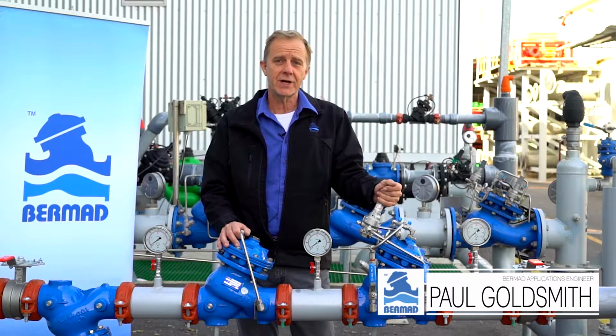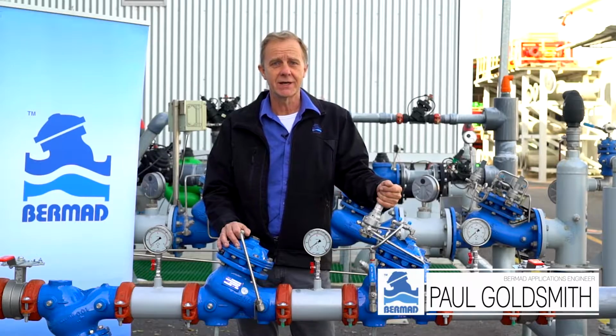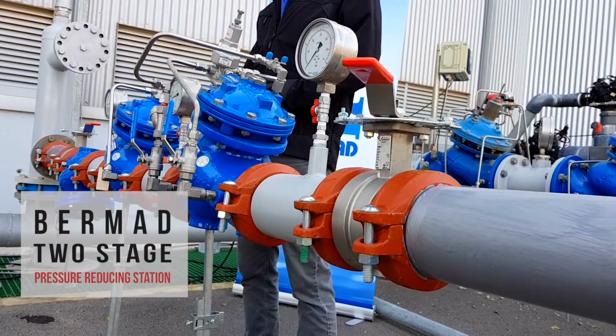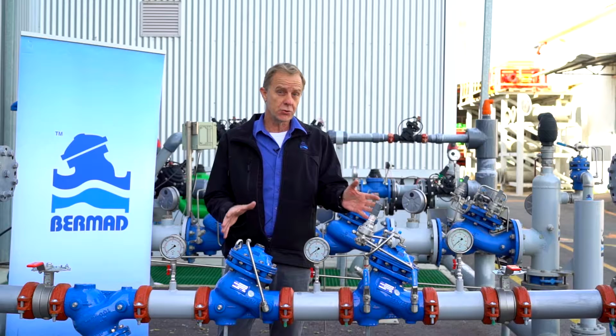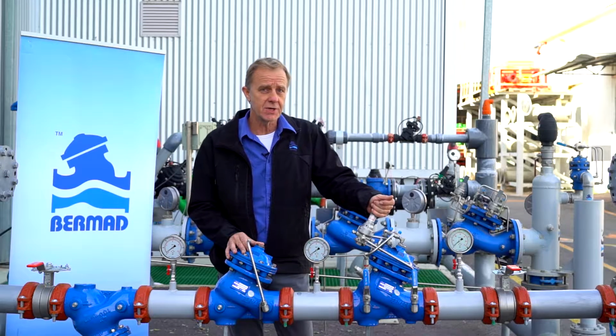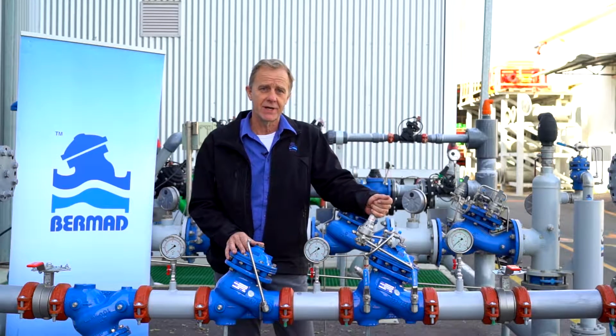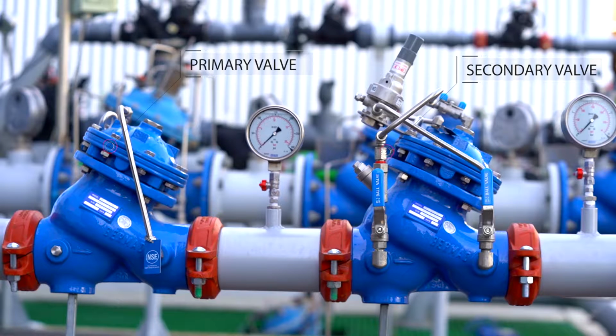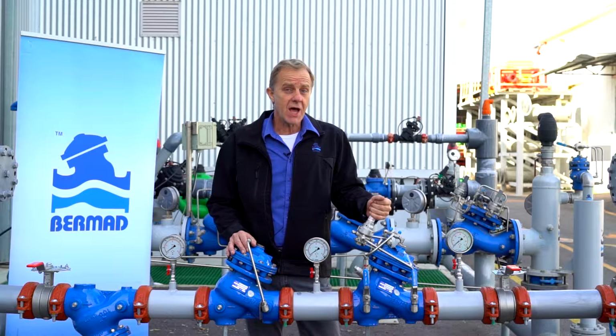In this video, we are going to talk about commissioning and maintaining the Bermad PRV two-stage pressure reducing station. This two-stage station is designed to be used where the pressure reduction is significant and the reducing load should be shared by two valves. This ensures high reliability and a safety consideration if one of the valves were to fail.